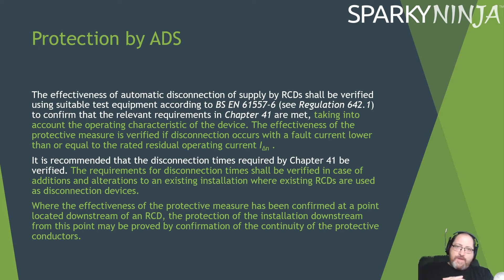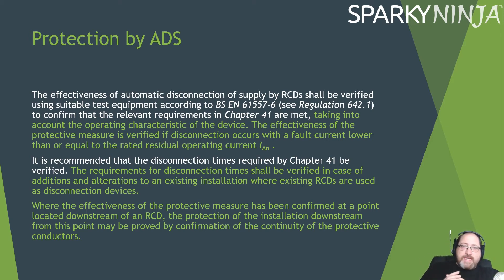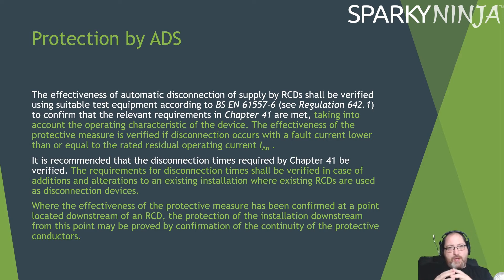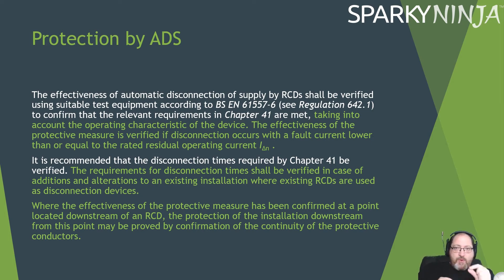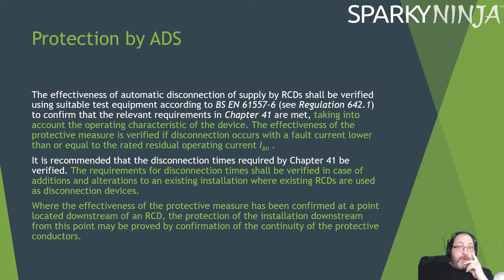The effectiveness of the automatic disconnection of supply for RCDs will be verified using suitable test equipment according to 61557. Take into account the operating characteristics of the device — the effectiveness of the protective measure is verified if disconnection occurs with a fault current lower than or equal to the rated operating current of the device. It is recommended that disconnection times required by Chapter 41 be verified, and this will be verified in case of additions and alterations where existing RCDs are used as disconnecting devices. Where the effectiveness has been confirmed downstream of an RCD, the protection downstream may be proved by confirmation of continuity of protective conductors.